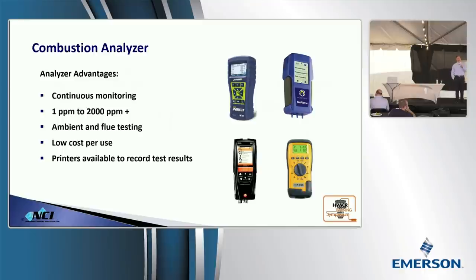Because number one, you have to start with the combustion readings, multiple combustion readings. The code tells us that we need to take one single air-free CO reading after 5 minutes of operation. It's insufficient. It doesn't tell you what the action of the flue gases are. You have to know if the CO is rising and if the oxygen's falling. That's unstable combustion. If you see that, guys, you got a problem. You got a time bomb, and it's just waiting for the right time to go off. We're getting ready to look at those readings and what they look like.